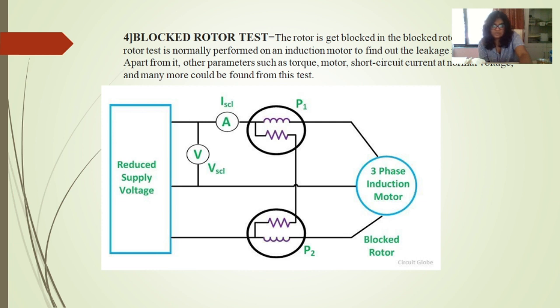A blocked rotor test is normally performed on an induction motor to find out the leakage impedance. Apart from it, other parameters such as torque, motor short circuit current at normal voltage, and many more could be found from this test. As you can observe in the figure, again there are 2 wattmeters connected. A reduced supply voltage is given to the 3-phase induction motor.